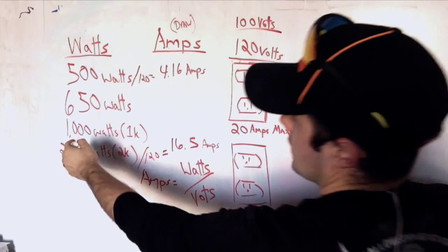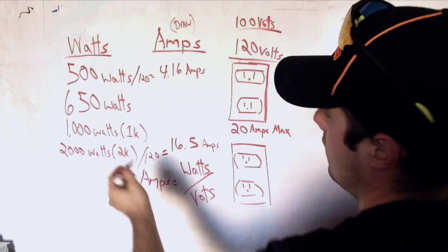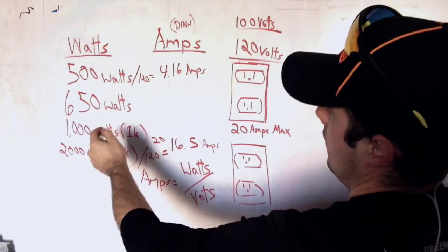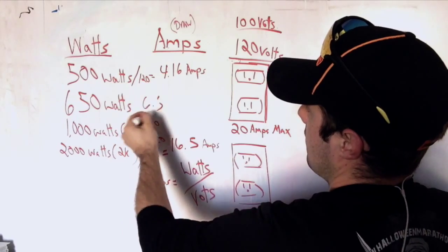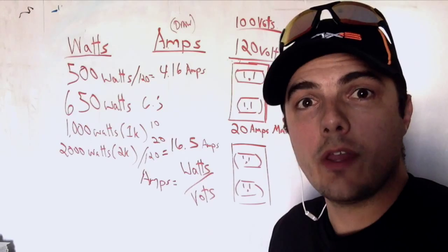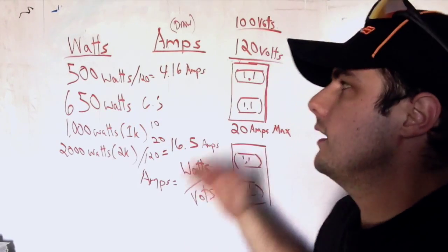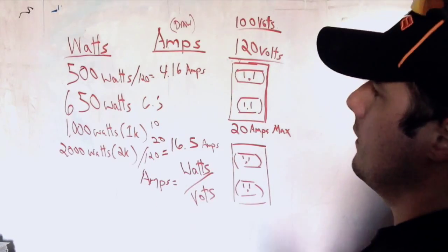So all of a sudden our 2000 watt turns into 20 amps. Our 1K turns into 10 amps, 650 turns to 6.5 amps, 500 watt turns into 5 amps. That's much easier math. So now we go okay, how many of these 500 watt lamps can I plug into a 20 amp circuit if I'm using 100 volts instead of 120? Well that means I can plug in four of them.